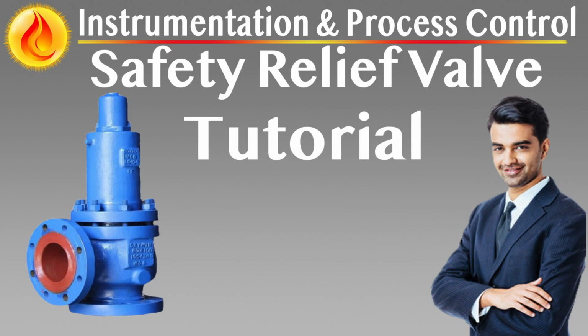Material and maintenance notes. These valves have simpler construction and fewer components compared to balanced or pilot-operated types, making them easier to maintain. The absence of bellows or pilots minimizes sensitivity to fouling or thermal cycling. However, they may exhibit greater wear or instability if subjected to fluctuating or excessive back pressure.